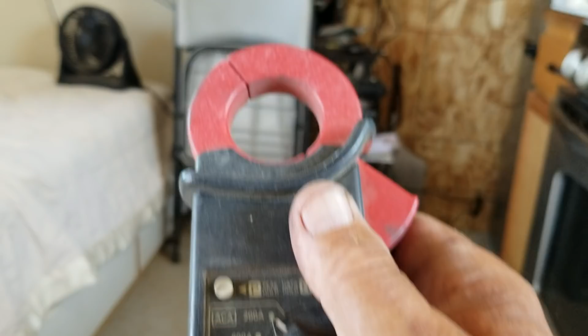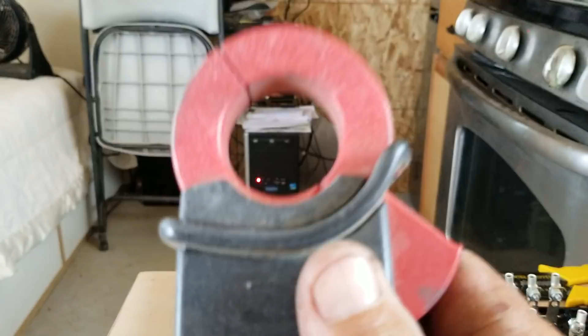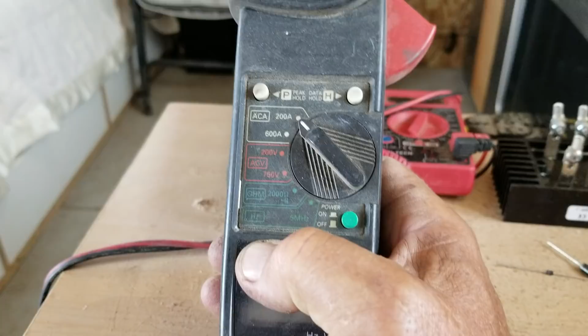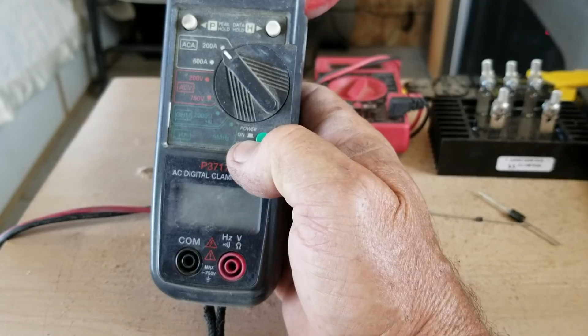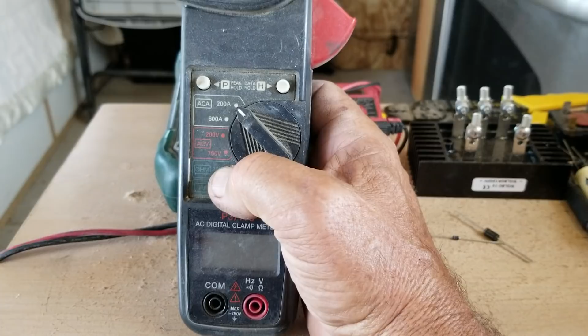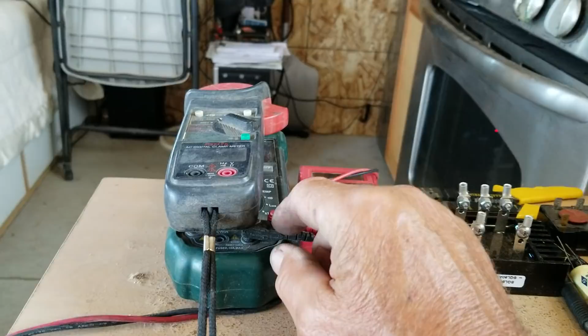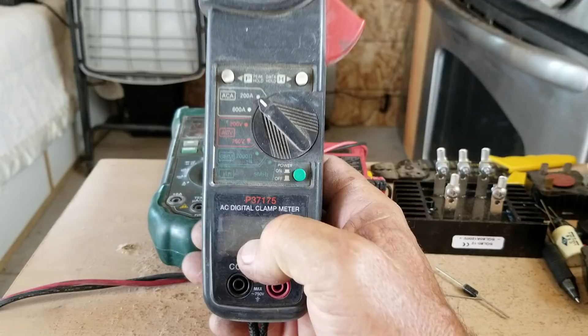This is a clamp-on amp probe. You can squeeze the trigger, put it around a live wire, and then read the amps when it's set on amps. That will tell you what type of amp draw a certain product or item is taking off the breaker. Now, you can't just put this around a plug cord like that one, because you have both a positive and a neutral running there. You want to put this around the positive wire only, so you have to go to the breaker and put it around there, or open up the outlet on the wall and put this around just the black wire.